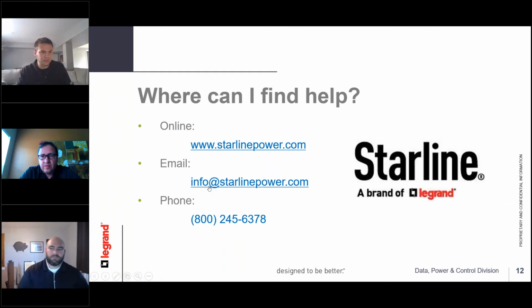Yeah. One of the benefits, especially in an industrial facility, is you don't always have to know exactly what's going there, or how long your cable is going to be. You might move a piece of equipment 10 feet over to the right-hand side, and you can do that easily with busway, because you either unplug it and move your busway plug over, or you have a cable length that's long enough. You basically just specify a 10-foot or a 20-foot cable length. If you don't need it, you loop it up, tie it up with a Kellems grip up top, and you're done. It's real simple and real flexible.